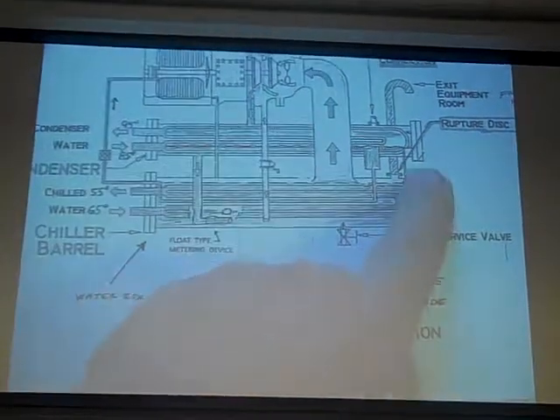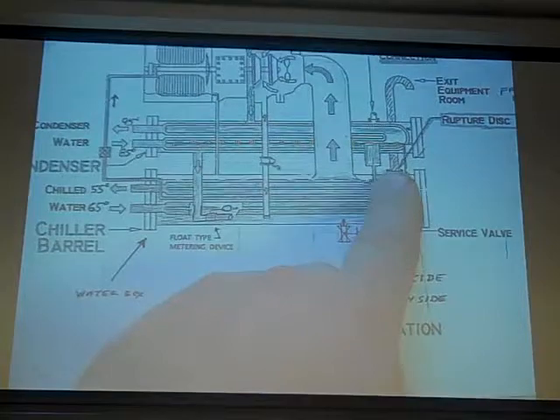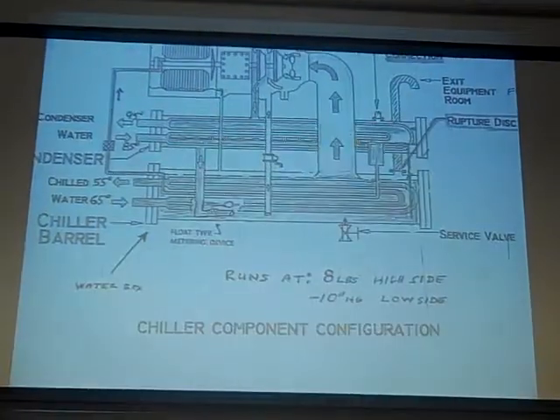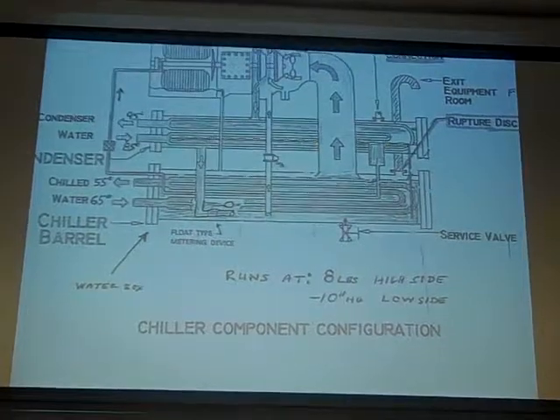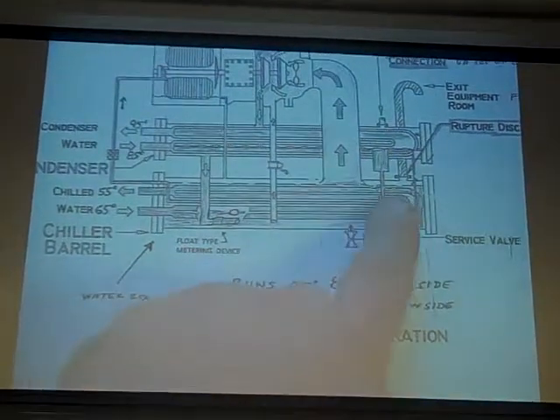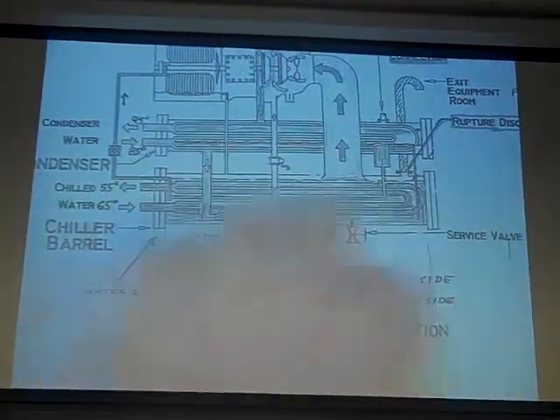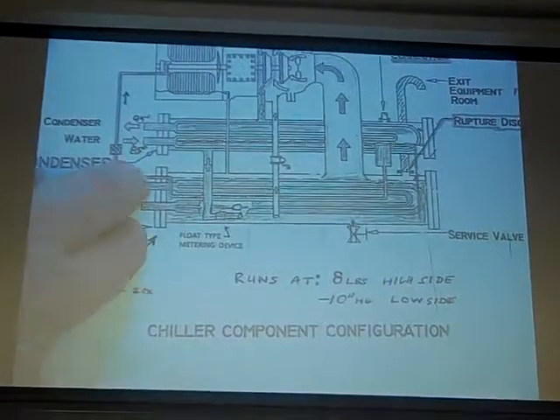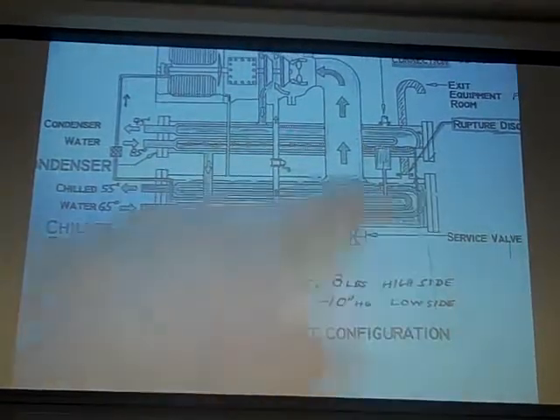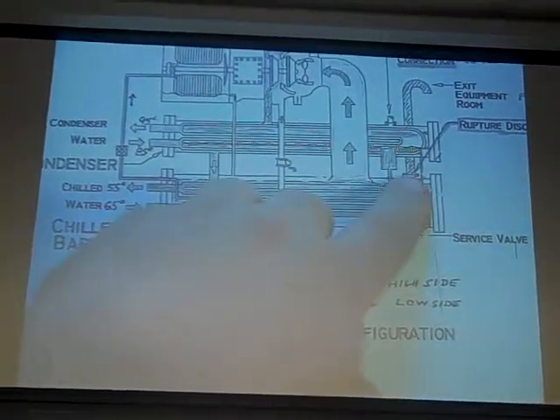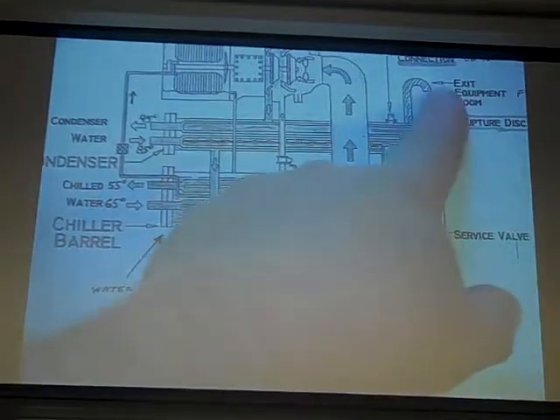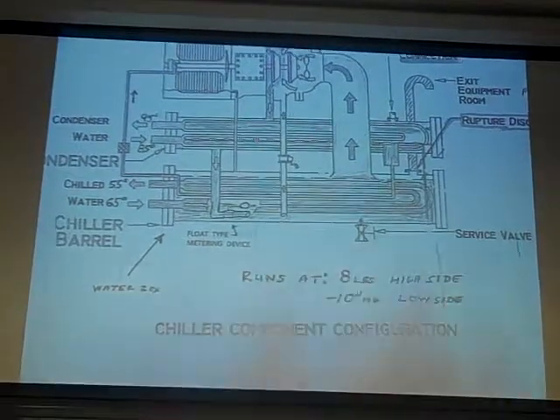This part right here, that's your rupture disc. That little disc right there. And it just goes up and vents out of the room, out to the atmosphere. It typically runs up to the roof somewhere. It vents off. So if you're sitting down here and you've got a bunch of liquid refrigerant down in here, this part's running at 10 inches of mercury. And for some reason, you dump a lot of hot water on that tube, you get it in there, you run that refrigerant pressure up above 15 PSI, that disc is going to bust, and all the refrigerant from in here goes right up here, to the roof. So you don't want to do that.